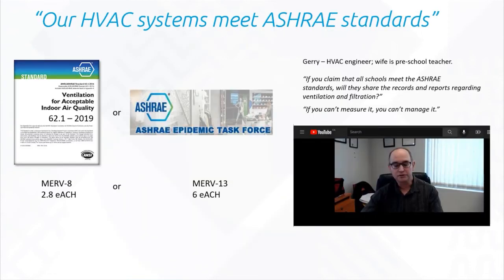Our HVAC systems meet ASHRAE standards. We see a lot of statements like this. So which standards? Do they meet 62.1, which was a couple of years ago, or do they meet ASHRAE Epidemic Task Force guidelines? Because with the Epidemic Task Force guidelines, the key changes are MERV 8 to MERV 13, and 2.8 air changes per hour is roughly the regular standard, and we're supposed to be shooting for 6. So just be careful about that as well, because the Epidemic Task Force guidelines are effectively the ones we're supposed to be shooting for right now.